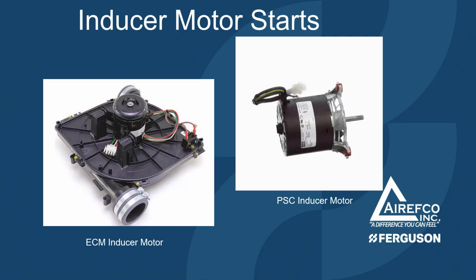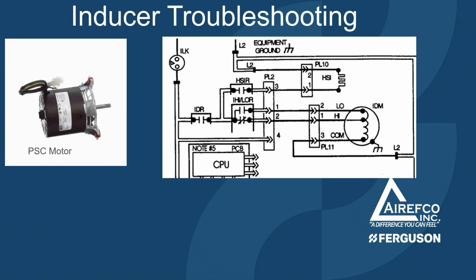The next thing that happens is the inducer motor starts. On most modern gas furnaces, you either have a PSC inducer motor or an ECM inducer motor. You need to be able to troubleshoot both. On a standard PSC inducer motor, you're going to have a number of leads that go to the motor. In this case, you have a low tap and a high tap and a common. So between the common and the low tap for heating, you should have your voltage to run the motor.